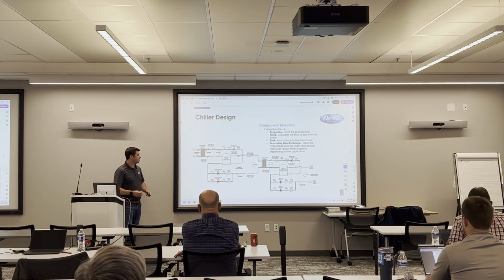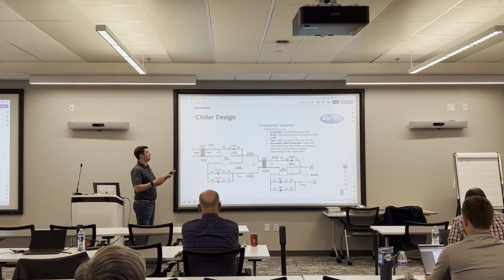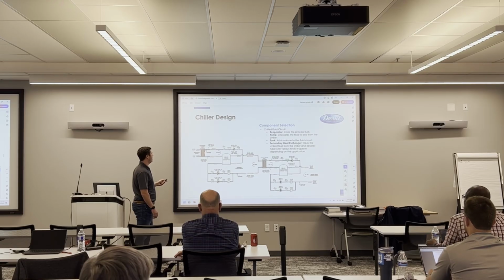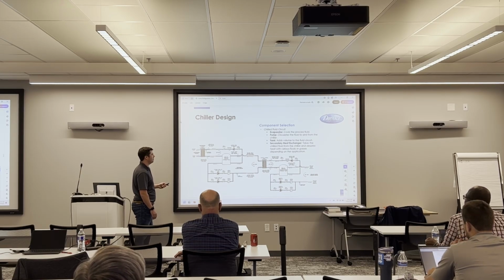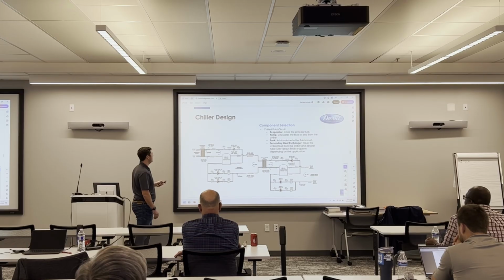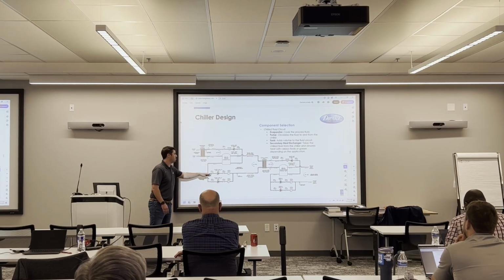But down below we'll go through this schematic here. They generally don't look this complex for us. I just wanted to get something up there to talk about. We'll go through each one here. So you're going to have your evaporator. Obviously, that's where the cooling's coming from. We'll have a glycol pump in this case, drawing from a large 300-gallon tank. It's going to send fluid into our evaporator and chill it. So maybe it's coming in at 50 degrees from the tank. It'll leave the evaporator at, we'll say, 40 degrees, and go back into the tank. And that's essentially how you're maintaining tank temperature.